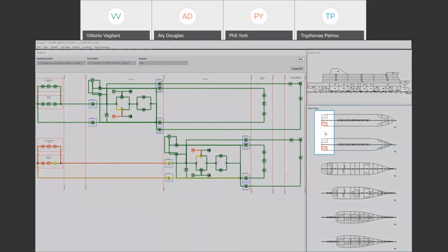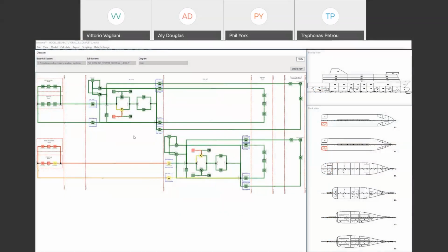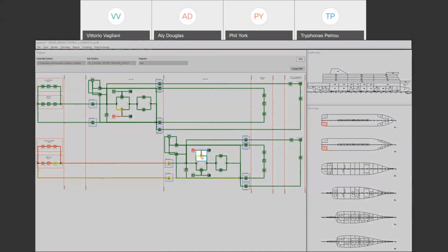The loss of the starboard pod unit's electrical control room will result in the damage of the I/O racks essential for pump control and operation. Subsequently, the functionality of the standby pump in the aft engine room, together with that of the running circulating pump in the forward engine room, is lost. This failure is not critical because there are 2 remaining pumps controlled by I/O racks placed in alternative locations for redundancy. If required, the affected pumps can be reinstated and operated locally.